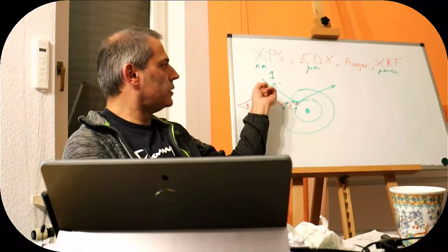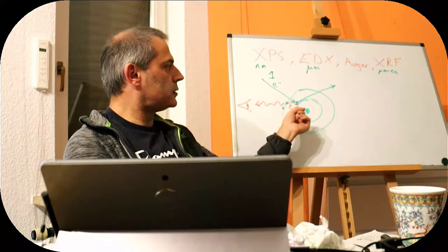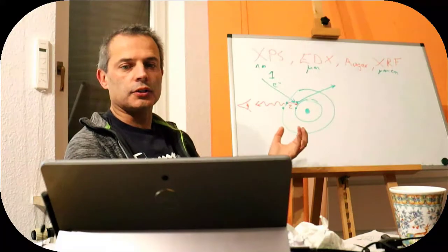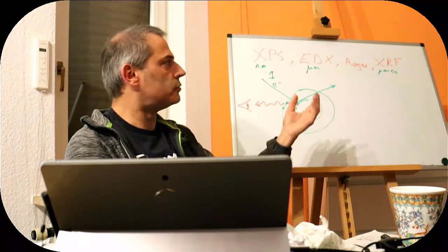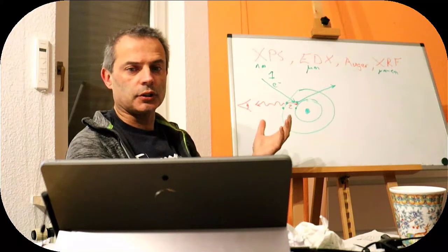First of all, the photon coming out doesn't care whether this atom is in a charged or uncharged environment, which is massively helpful if we're doing EDX in an electron microscope, for example, where we might not be able to control charging.